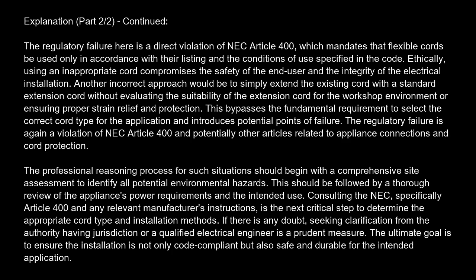Another incorrect approach would be to simply extend the existing cord with a standard extension cord without evaluating the suitability of the extension cord for the workshop environment or ensuring proper strain relief and protection. This bypasses the fundamental requirement to select the correct cord type for the application and introduces potential points of failure. The regulatory failure is again a violation of NEC Article 400 and potentially other articles related to appliance connections and cord protection.